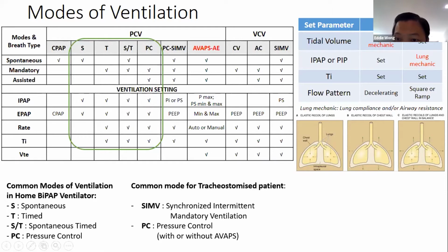If you look at this table on the top right here, you will see that under pressure control modes, the tidal volume you cannot set. It depends on the lung mechanics of the patient. You can only set IPAP, EPAP, I time, and the flow also cannot be set, it is always fixed as decelerating. Okay, you do not need to understand this, but I need you to understand what lung mechanics is.